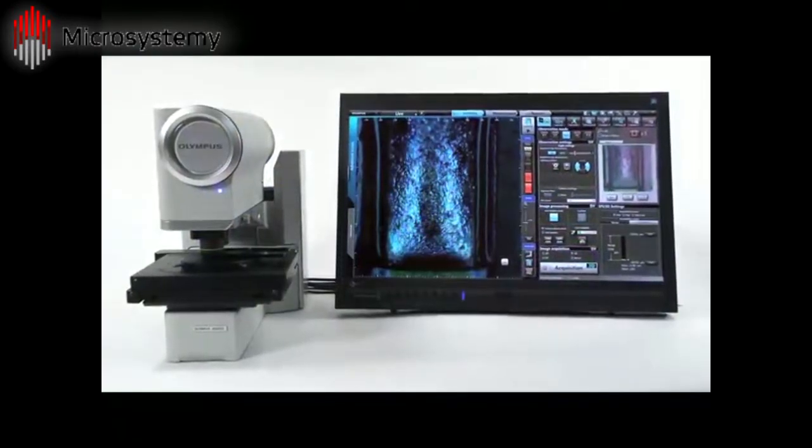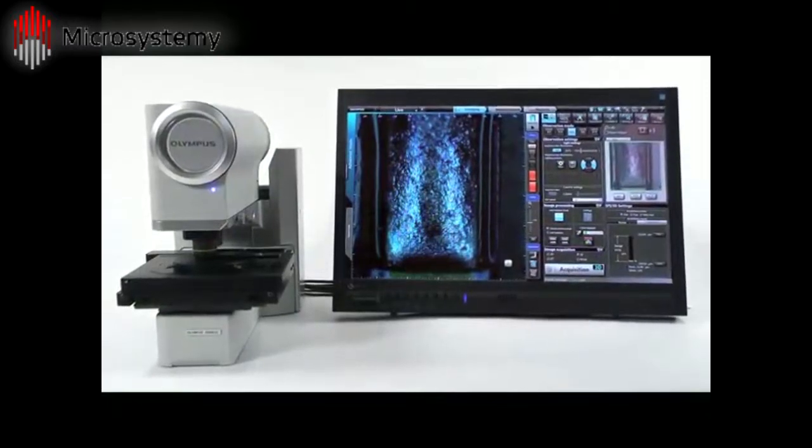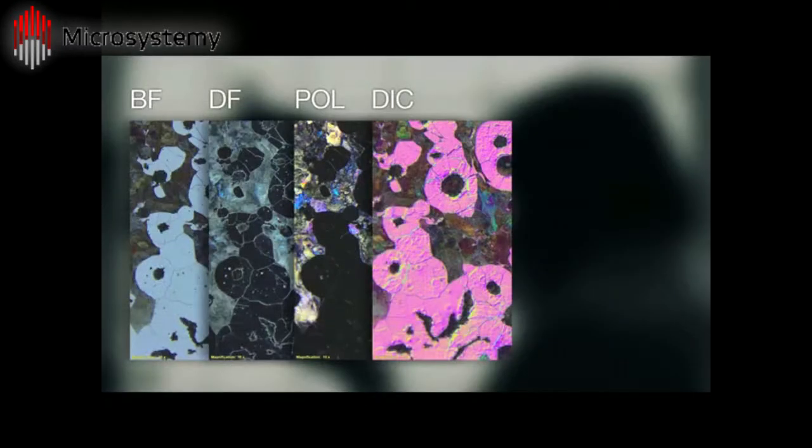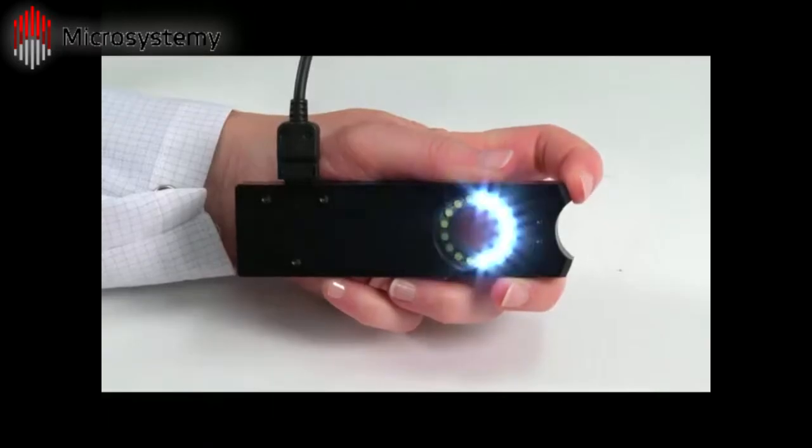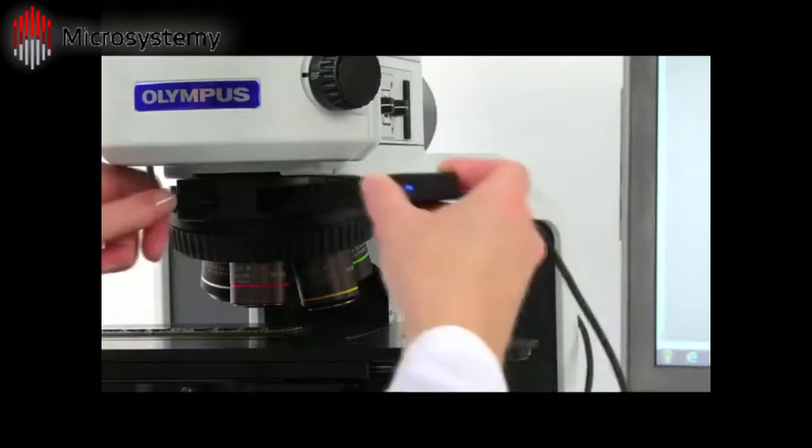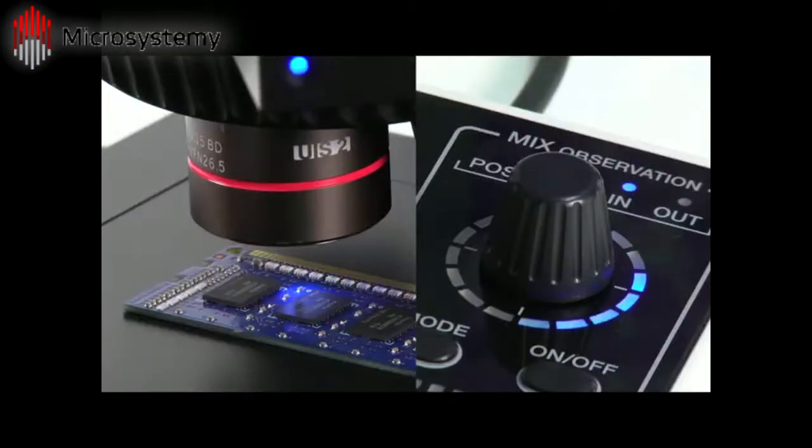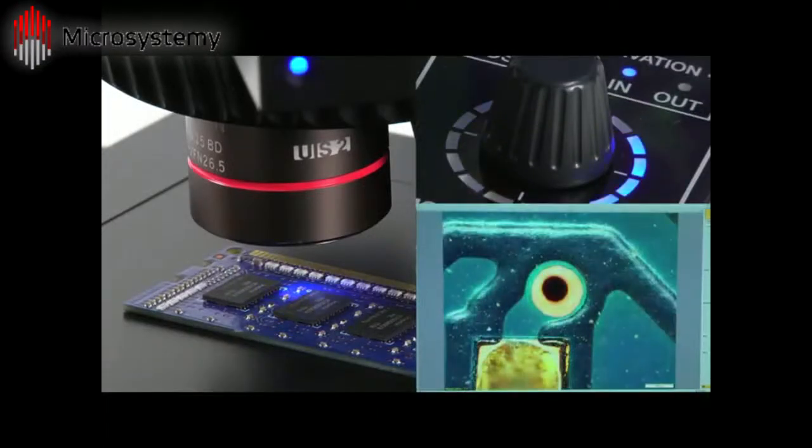Based on technology from our DSX digital microscopes, the BX3M also offers Olympus directional dark field and mix illumination. The 16 LEDs in the mix slider shine directional dark field on the sample, similar to traditional dark field but with more flexibility.